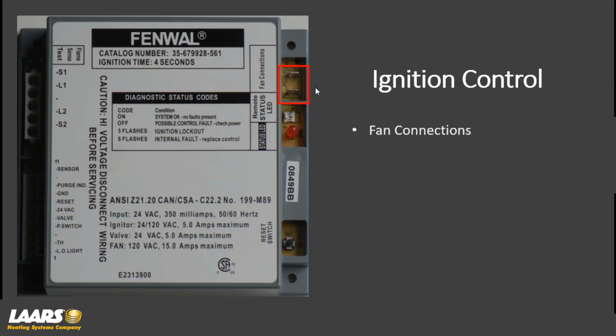So we'll power the combustion air blowers from the ignition controls on the MightyTherm2. So when an ignition control goes into a lockout, hypothetically, let's say we had a weak igniter and it went into a lockout, it also shuts the fan off. Okay. Keep in mind, if we're doing combustion air ducted to outside, maybe you're in cold climate, it's 0 degrees out some night, the boiler locks out because of a weak igniter, for example. We don't want to be pulling in 0 degree air and freeze a tube on the heat exchanger. So the fans do shut off during a safety lockout.